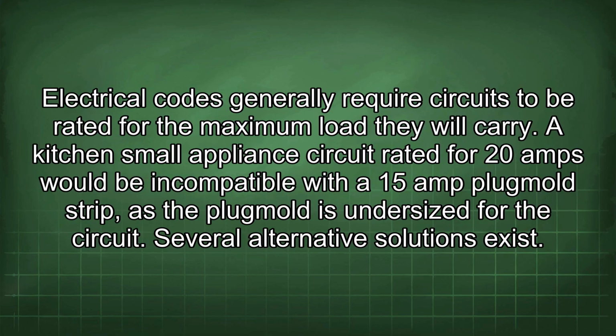Electrical codes generally require circuits to be rated for the maximum load they will carry. A kitchen small appliance circuit rated for 20 amps would be incompatible with a 15 amp Plugmold strip, as the Plugmold is undersized for the circuit.